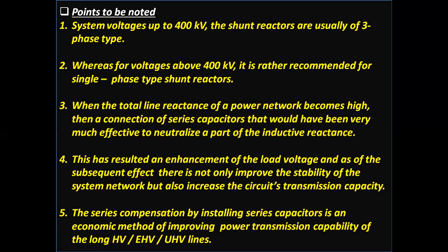Points to be noted. 1. For system voltages up to 400 kV, the shunt reactors are usually of three-phase type. Whereas, number 2, for voltages above 400 kV, it is rather recommended to use single-phase type shunt reactors.